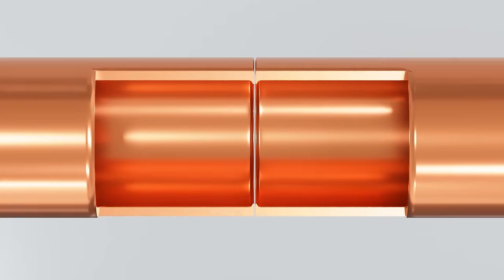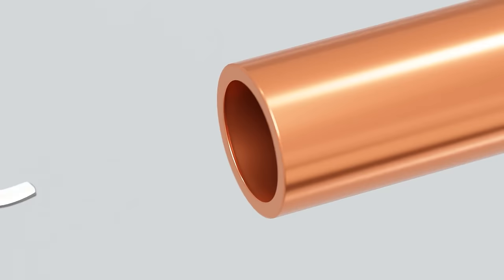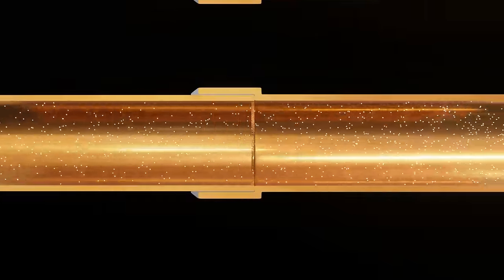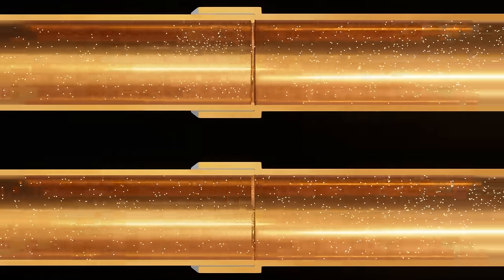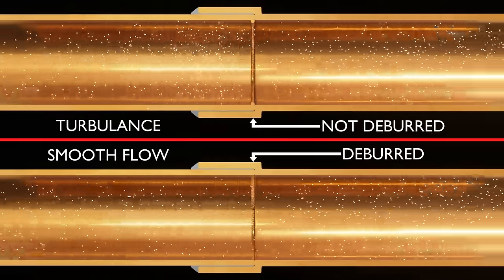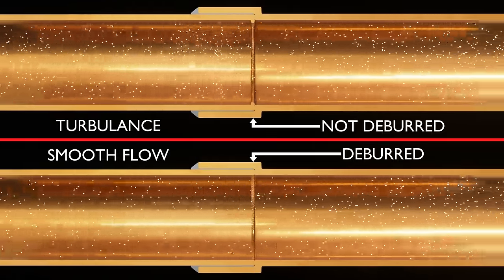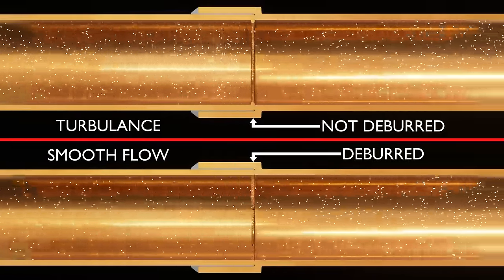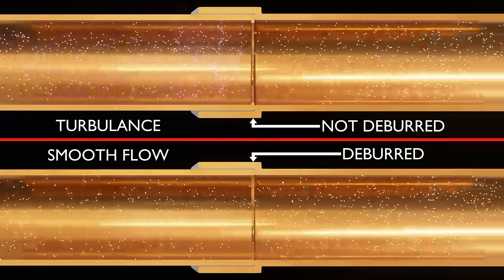This burr can create turbulence if left in place. Use the deburring tool to remove the burr and ensure that burr or particles do not fall into the tubing. Some techs in critical situations will opt to use needle-nose pliers, inserting them into the tube and twisting back and forth rather than risk dropping shavings into the tubing with a deburring tool. Use your judgment and your own company policies where these situations might apply.